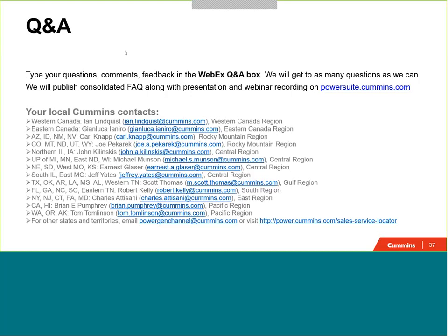Yeah, good question. So there are many places we see this 100% load requirement specified, and often it is required from an owner standpoint or from a site standpoint regardless. I'd say this is conducted almost always with site testing as a requirement or as an acceptance requirement for a product on site. And again, as I mentioned in my previous comment about diesel and natural gas products, be aware of what different vendors are able to provide.